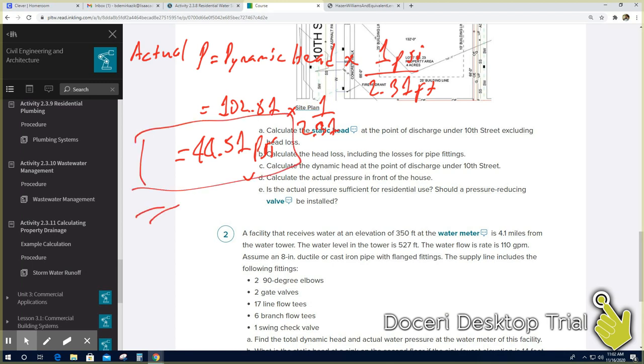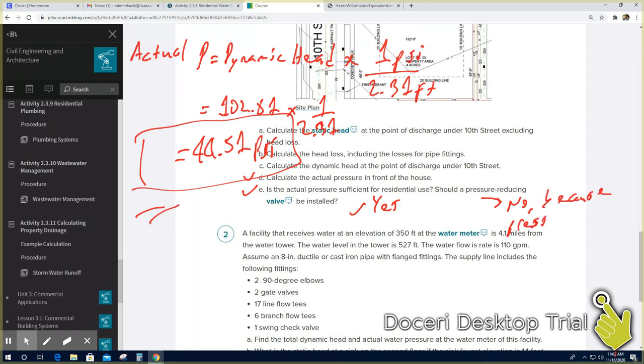For E: is the actual pressure sufficient for residential use? Yes, because it should be between 40 and 80 psi, and 44.51 psi falls within that range. Should a pressure reducing valve be installed? No, because the pressure is sufficient. I hope this video helps you solve questions A through E — have a wonderful day!